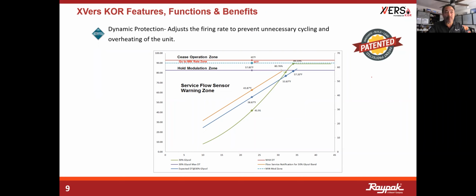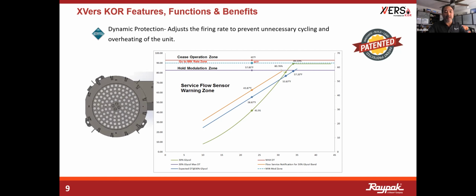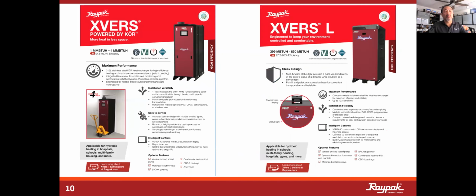Because the bottom line is, if you put more glycol in the system, it doesn't matter how many BTUs that boiler is capable of, unless you are pumping it faster, you won't be able to transfer the heat into the water, and it will therefore go into the material and just stress the heat exchanger. So the bottom line goal of this is to ensure that we maximize the lifetime of that heat exchanger. And I can tell you today, in the 5 years that we've had the XVers and the XVers with KOR out, we have not seen a single heat exchanger failure.